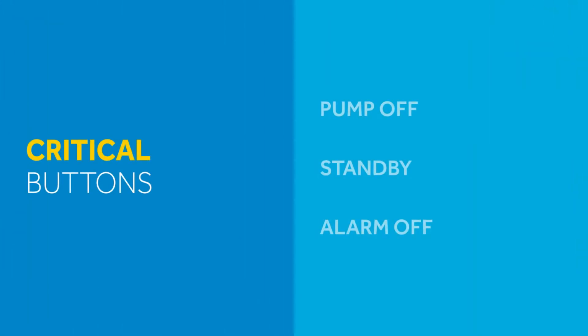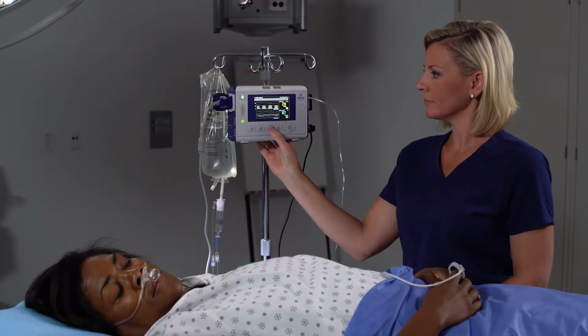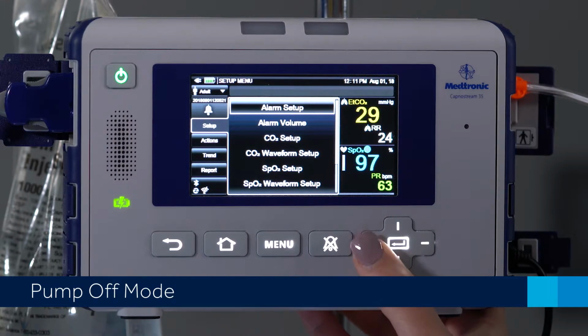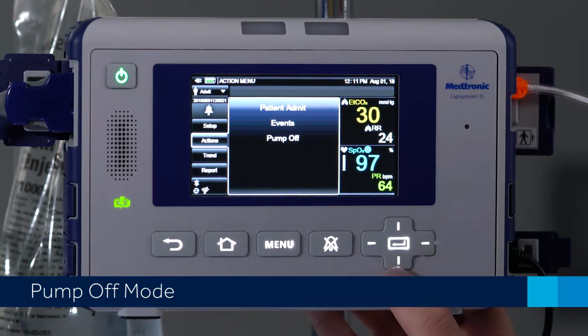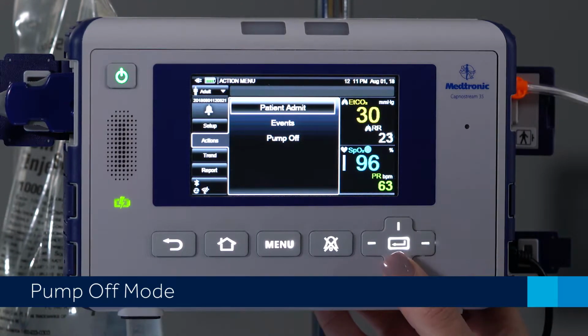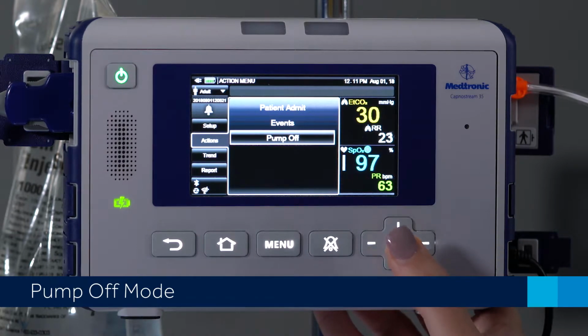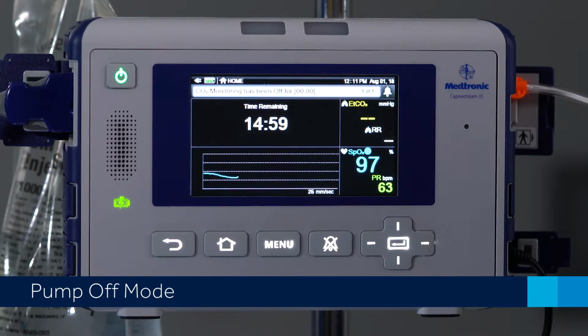Now these 3 buttons are important to understand and they will be your best friends. They help minimize nuisance alarms. It's important to note the standby mode will need to be enabled in institutional default settings. To set pump off mode, the monitor must be currently monitoring CO2. Click the menu button, select Actions, then Pump Off. Hit Enter. The standard pump off period is 15 minutes. Time remaining will be displayed on the monitor.